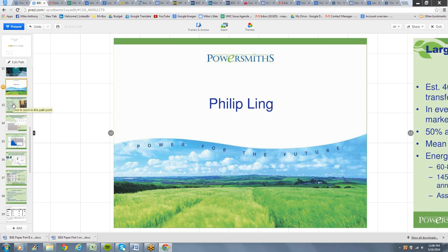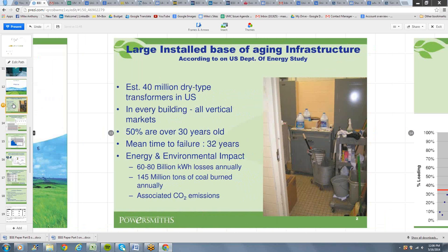Thanks, Mike. Yeah, the transformer is a pretty interesting beast, actually. It's one of those things that's behind closed doors, locked away in a closet somewhere. Once it's installed, no one really pays much attention to it, as you can see in this picture. There are about 40 million dry-type transformers installed across the country, and statistically, it's important that we understand about half of them are over 30 years old. With a mean time to failure of 32 years, you can see a pretty good conflict, or a change-up, that's going to be required over that time. The environmental impact is substantial.